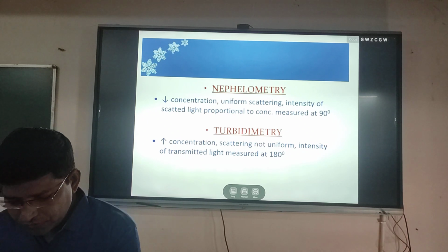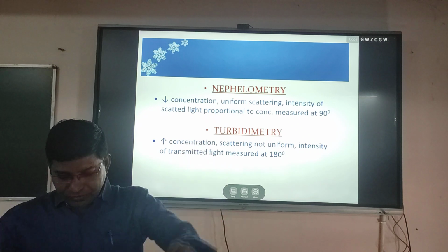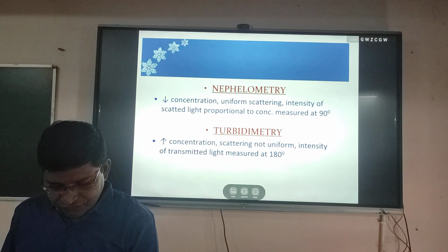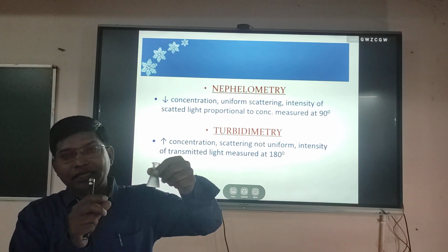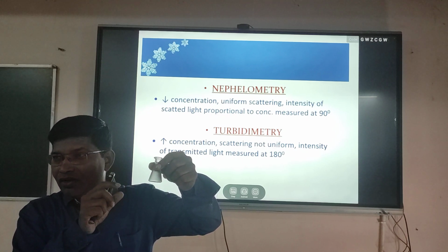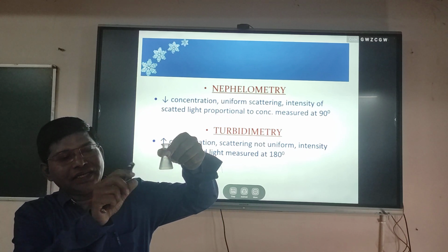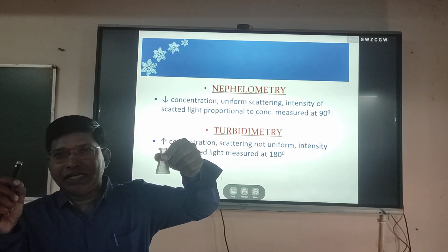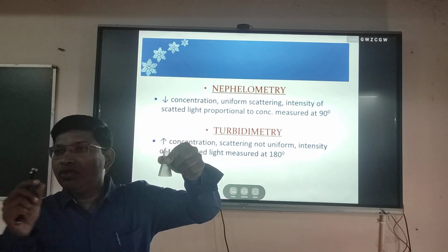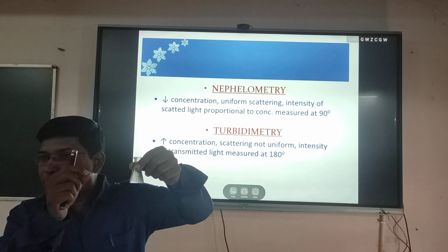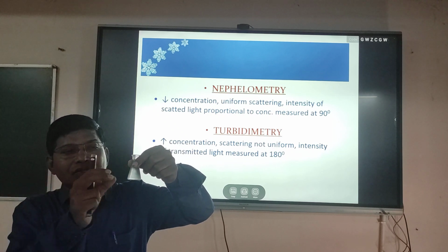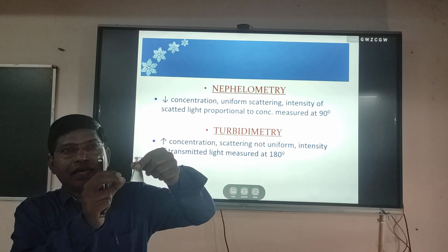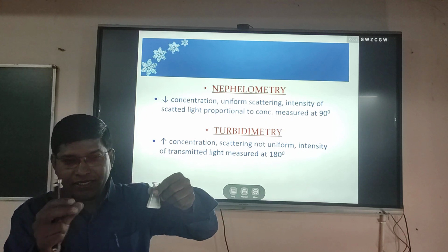We prefer nephelometry when the concentration is low, where the suspended solid particles are more towards uniform size, so we get better scattering.